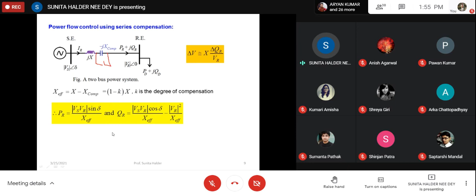In that case, PR equals VSVR sin delta divided by the effective X, and QR will also improve, meaning the voltage drop improves too, though the effect is greater on active power than reactive power. So series compensation is also used in power transmission systems, but it is more effective for active power transfer than reactive power control, with its disadvantage being the risk of series resonance.